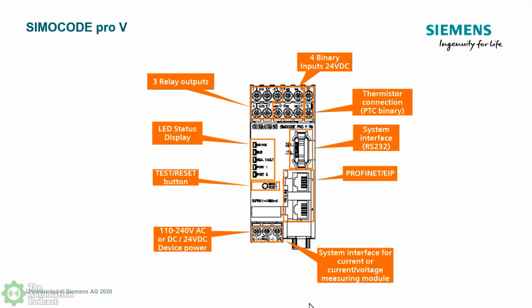Then you have a thermistor. Some customers I ran across too, after 150 horse motor, they'll put a thermistor in the stator. And then the communication protocol to talk to the other modules is RS-232. And then, of course, we're emphasizing today the TCP/IP protocol, Profinet, and Ethernet IP. There's a 2-port switch that you can use there, and it's a dumb switch. It can allow you to do star topology, token ring, or if you want, don't recommend it, but if you want to just do daisy chain.